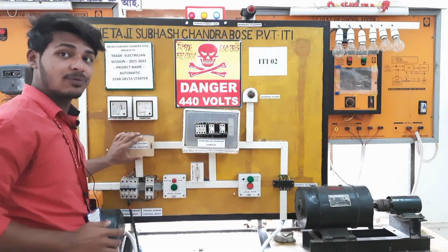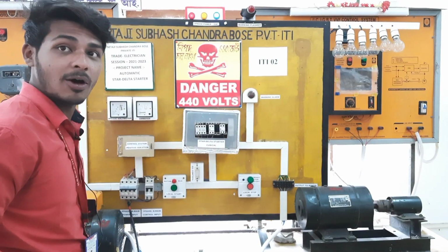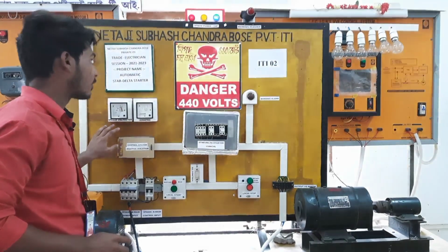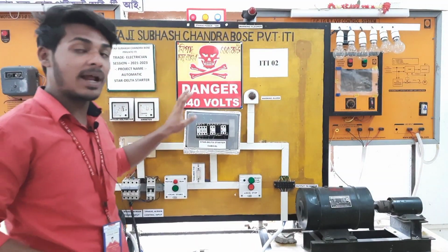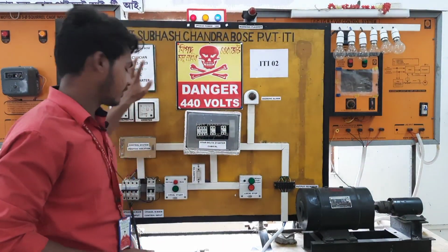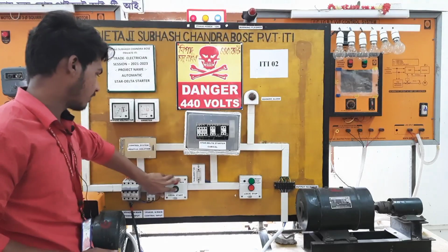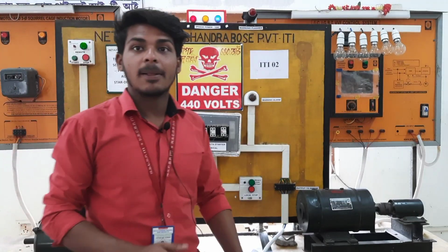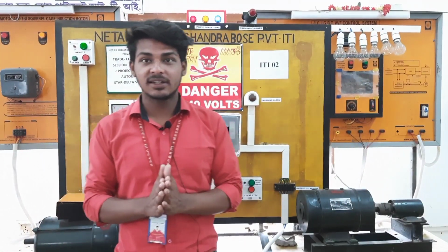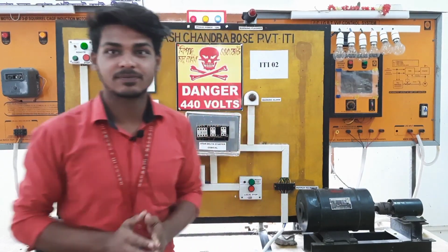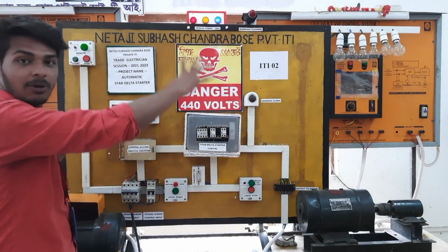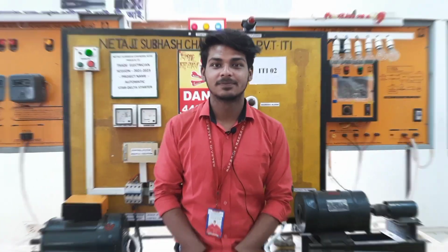Now we have introduced the special protection called positive isolation. In that case, if we lock the control system with a lock, nobody can operate our motor. Even though control and power supply is available here, the motor cannot be started. This is used for maintenance protection or idle protection. That's all our operation. Thank you.